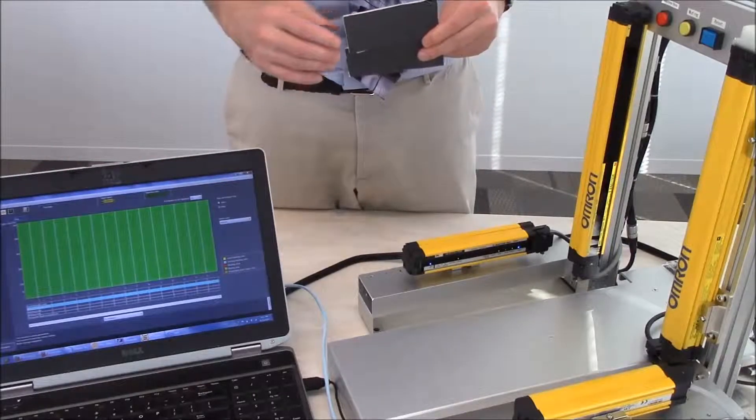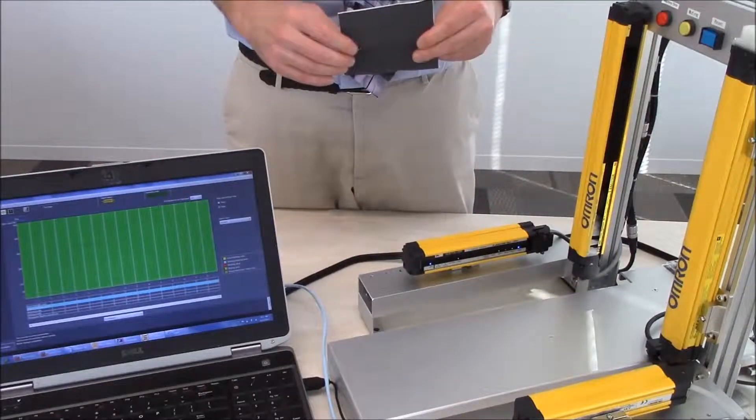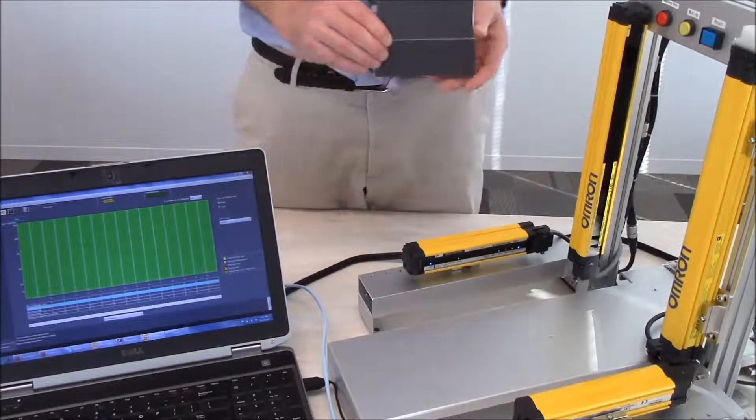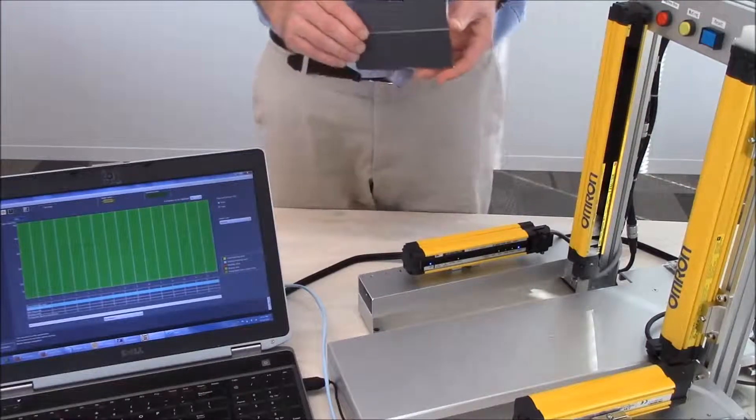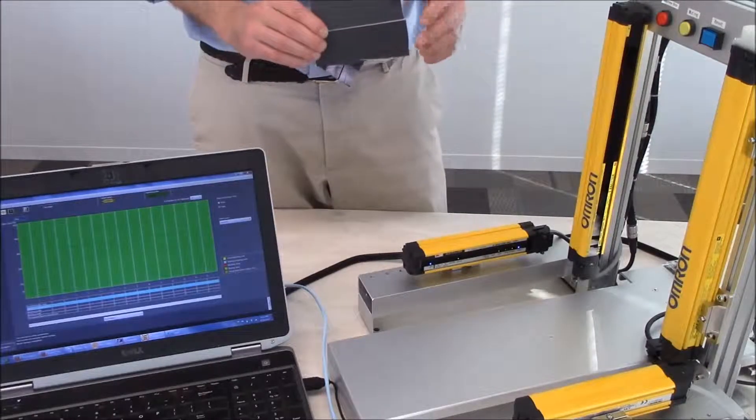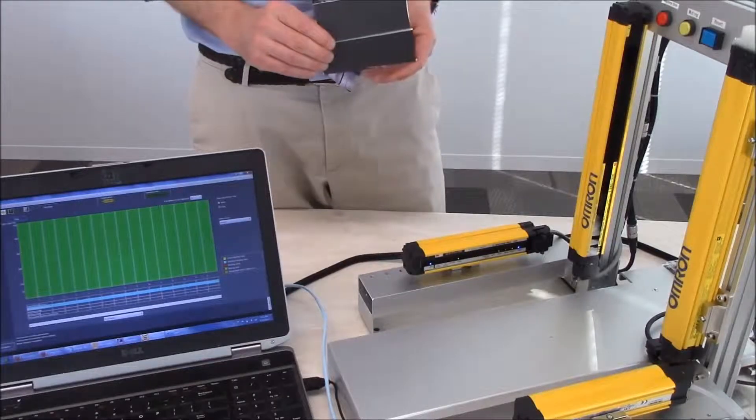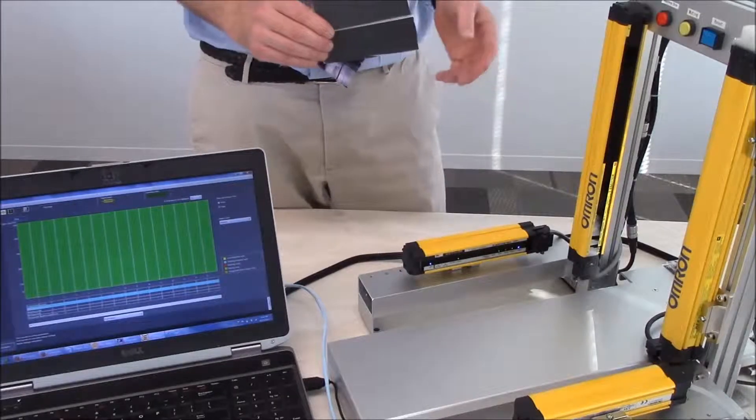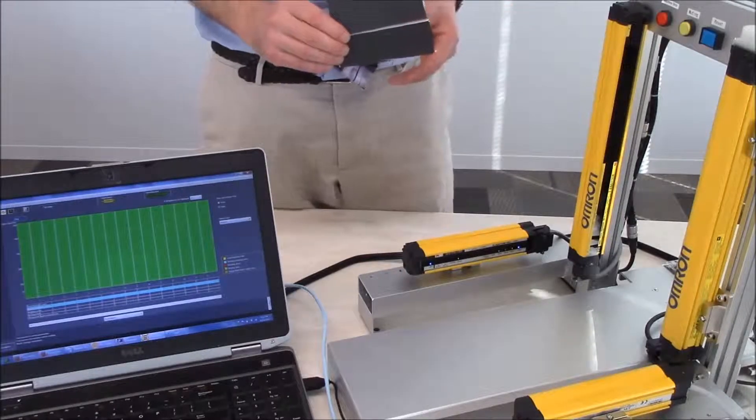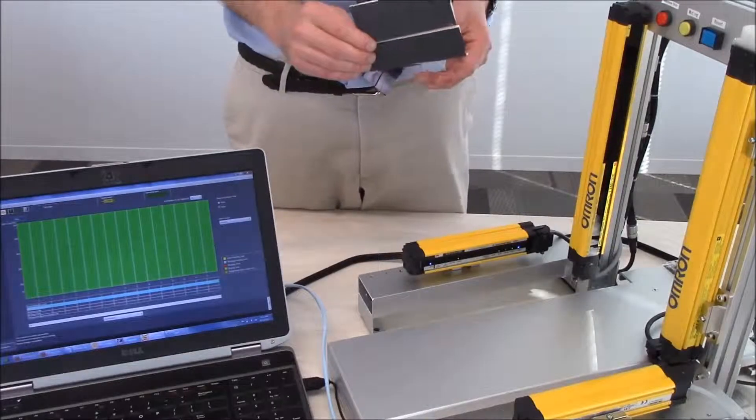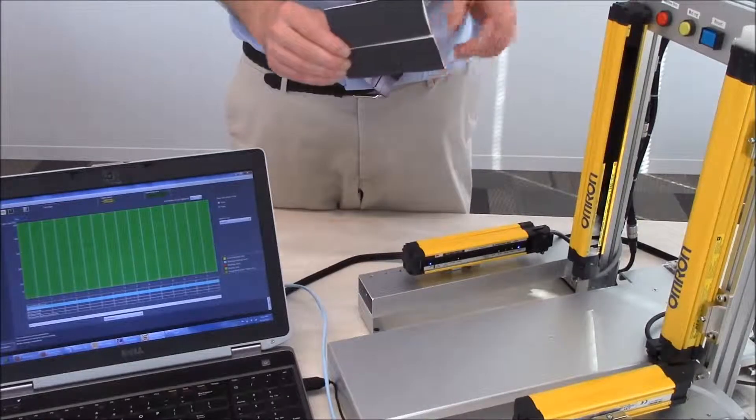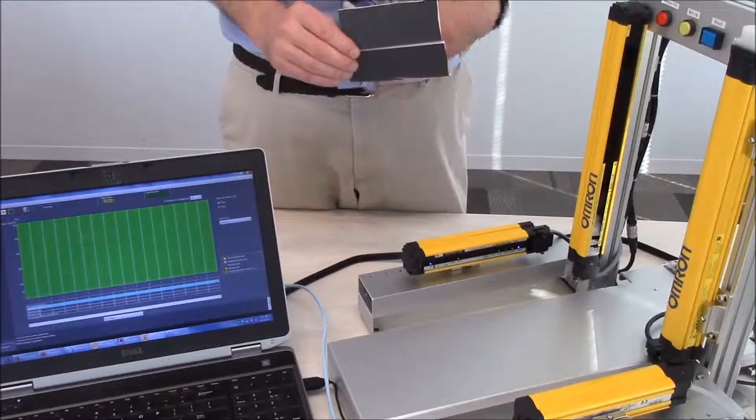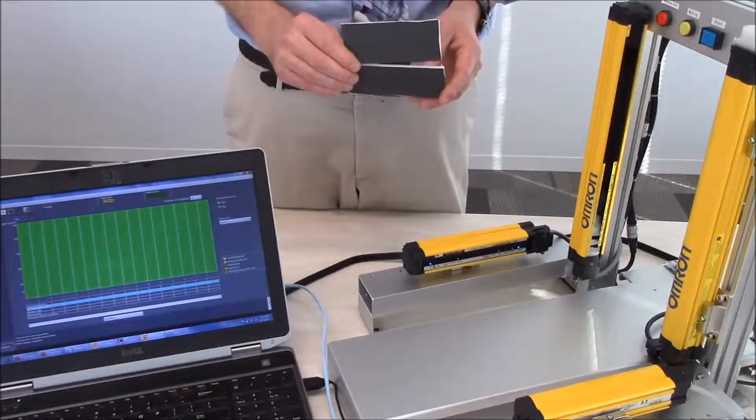Now the thing that is kind of nice about the reduced resolution feature is it is similar to a floating blanking condition. But with floating blanking you need to have consecutive beams blocked in order to satisfy the light curtain. Now with the reduced resolution that allows you to do multiple items.